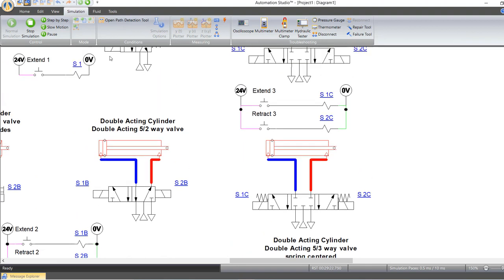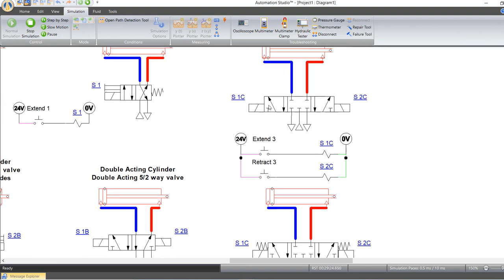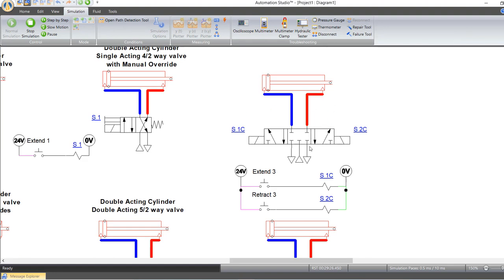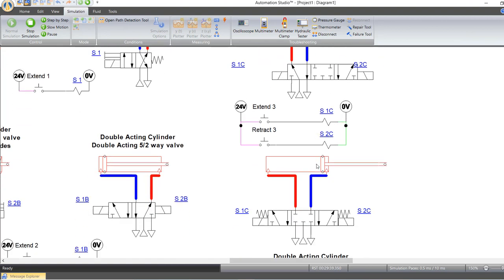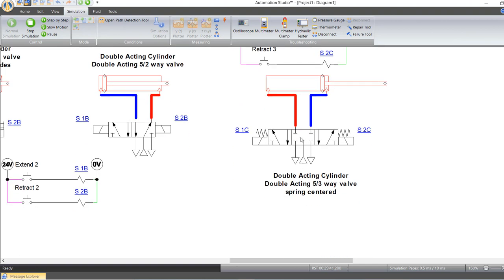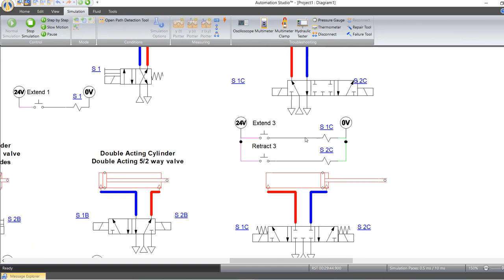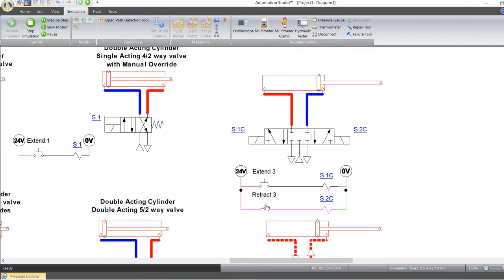So if we look at this particular thing, the top one, which I mentioned was missing the springs, if you press this, you'll see the left position goes in place. Solenoid's not activated anymore. This should actually have slid or switched back to the center position like this one did. Activate this.